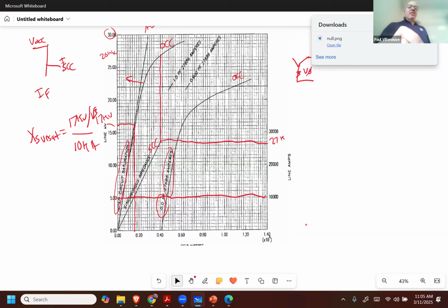Well, I know that I need to be saturated. I need to be someplace above the knee of the curve. And I'm assuming that the slope of the line above the knee of the curve is fairly constant. So it's the best that I can do. It would be better to go a little bit further away, but you can see that it's kind of rounded the corner already, and it looks like it's leveling off. So it appears that it's going to be straight the rest of the way. But again, that's the best I can do. So I'm going to go with that.